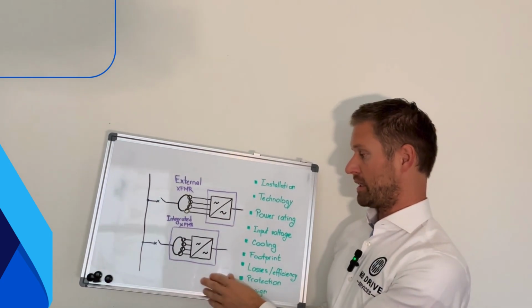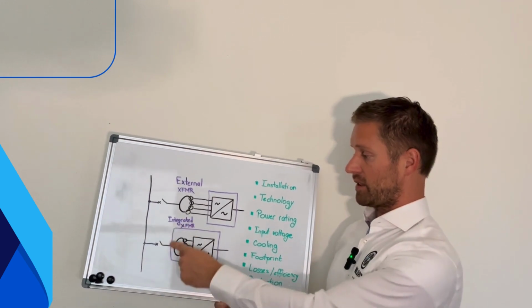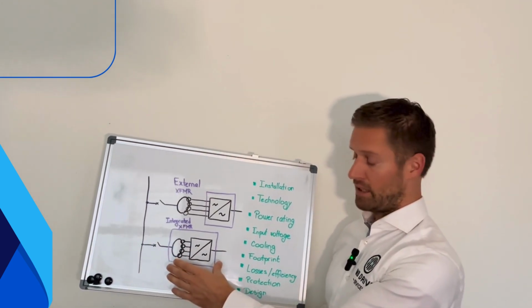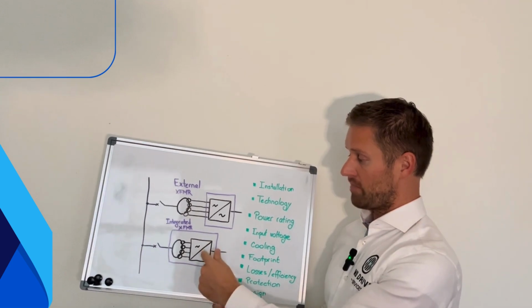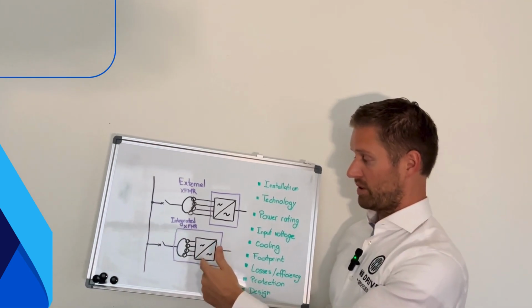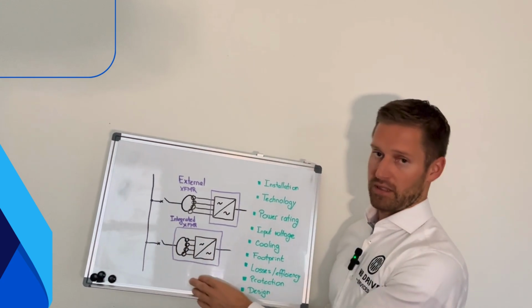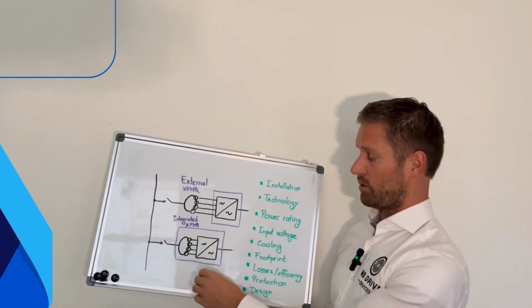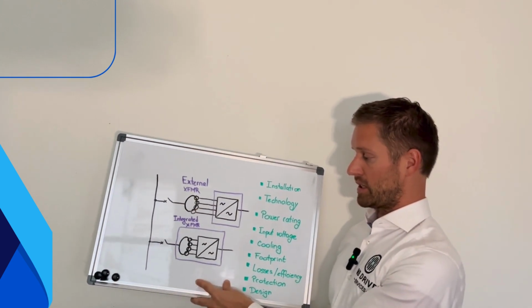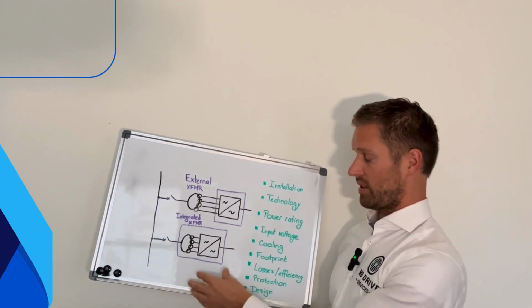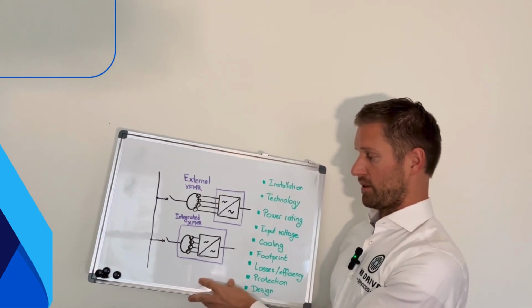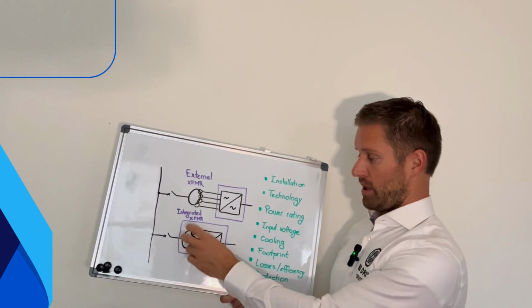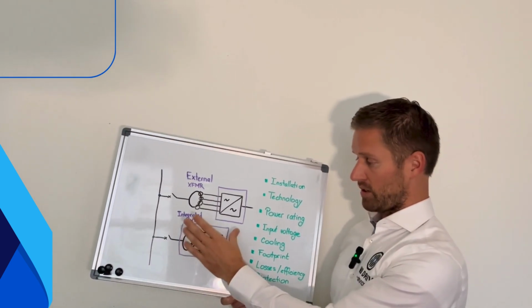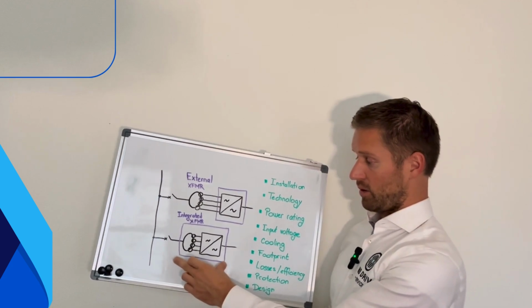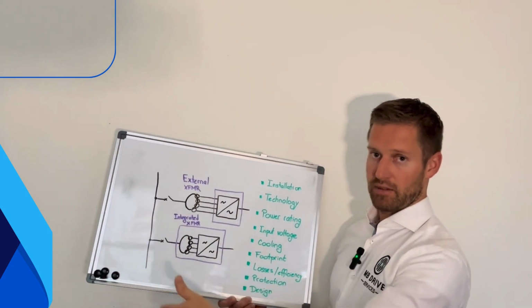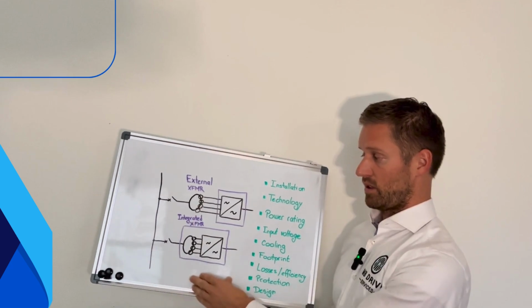Protection: here we have quite a major difference. If the transformer is integrated, so it's part of the VFD, then the VFD manufacturer shall and also does provide the protection of the transformer. So there is typically overcurrent protection, there is some protection for the insulation system, like surge arresters for overvoltages, and so on. So at least the minimum transformer protection is already included there, and it's also tested already in the VFD factory at the end of or after the production as part of the routine tests.